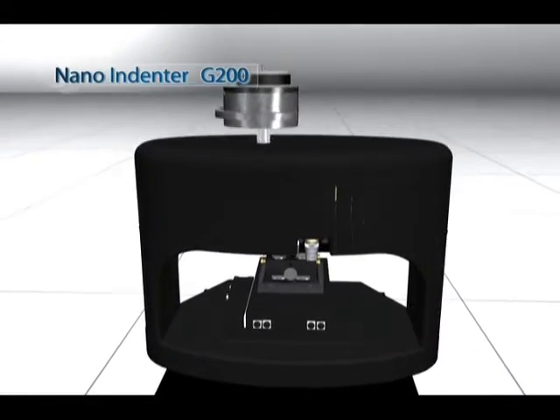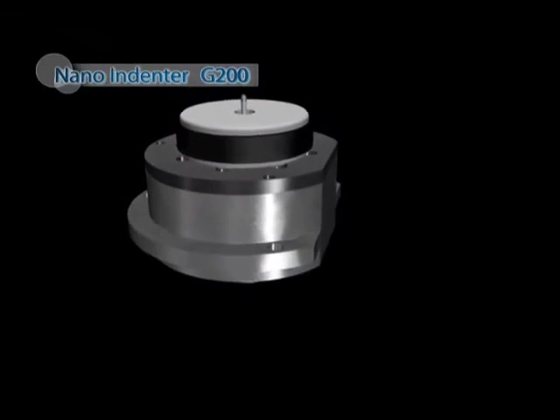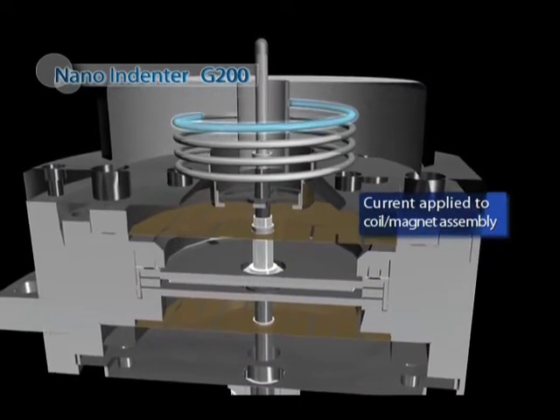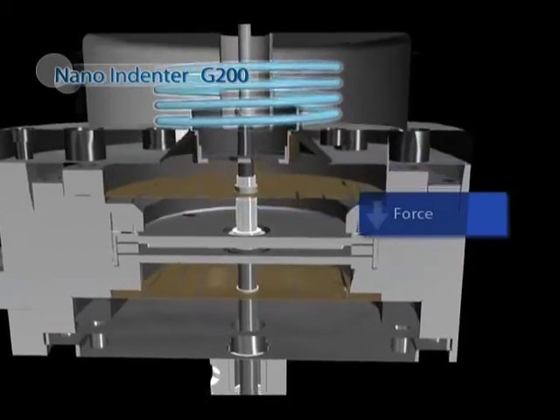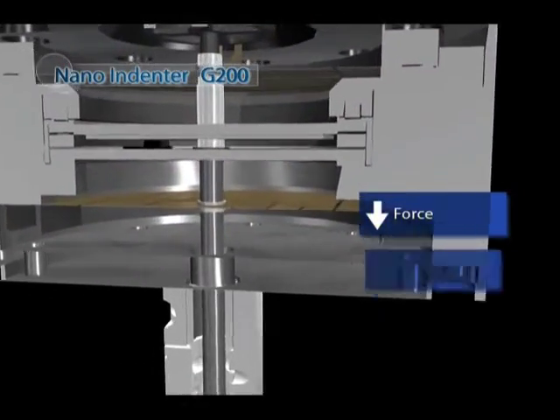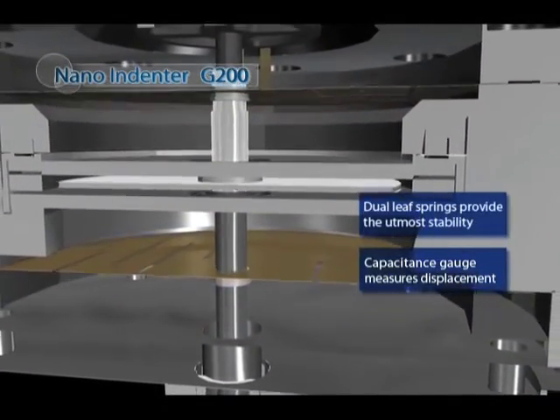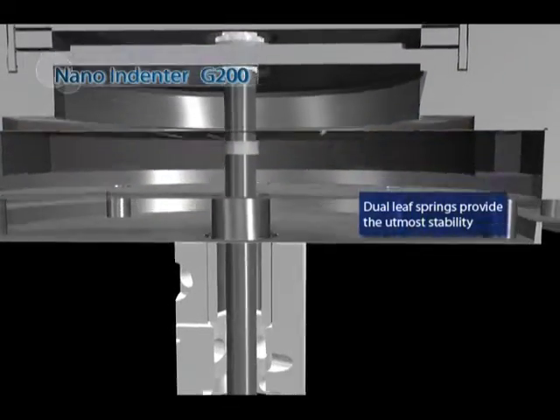The core technology of the nano indenter uses independent means for force application and displacement measurement. Force is generated in the transducer using electromagnetic actuation, and the resulting displacement is measured using a capacitive gauge.